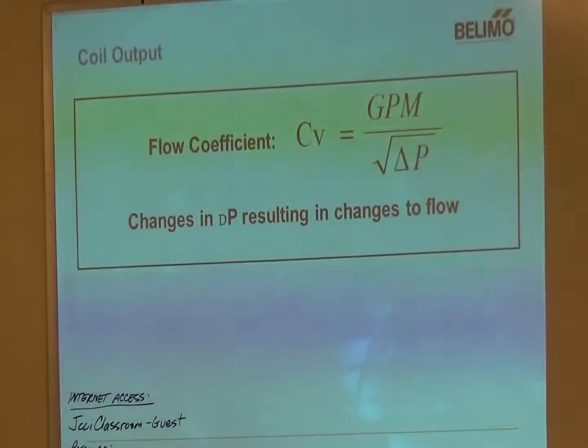We want the pressure to be between 5 and 50 psi across your pressure independent valve to maintain the pressure independence. If you're outside of those ranges, the valve will still work, but then it'll start working like a pressure dependent valve in that you will see differences based on pressure fluctuations. And that's more true in a mechanical pressure independent valve than an electronic pressure independent valve. Right. Which one is this? The energy valve that we're going to be talking about is an electronic, so you don't see that as much. We can actually be pressure independent down to 1 psi on the electronic pressure independent valves.